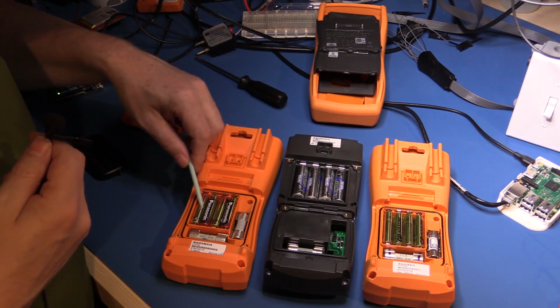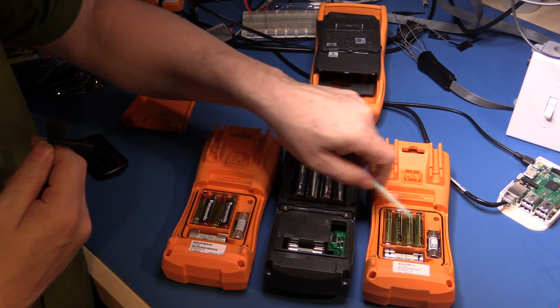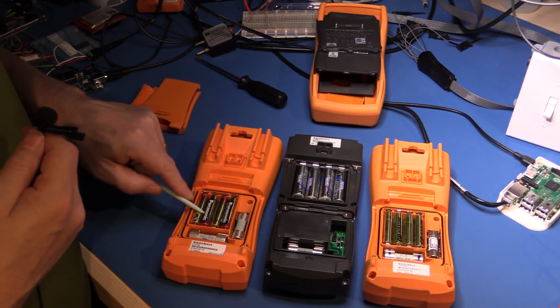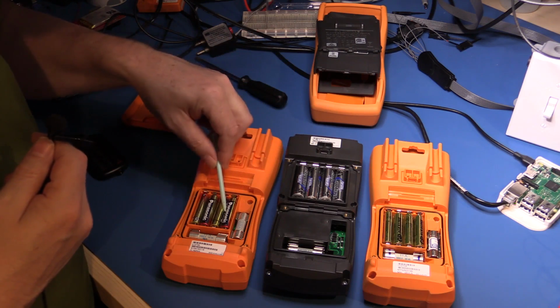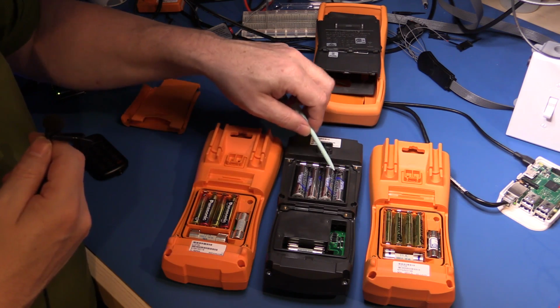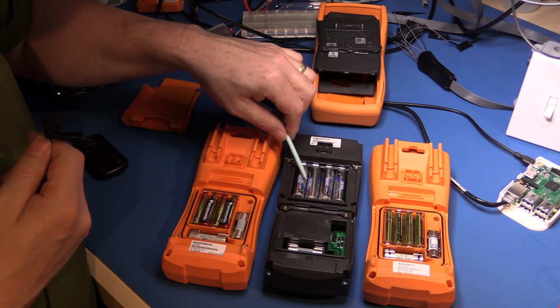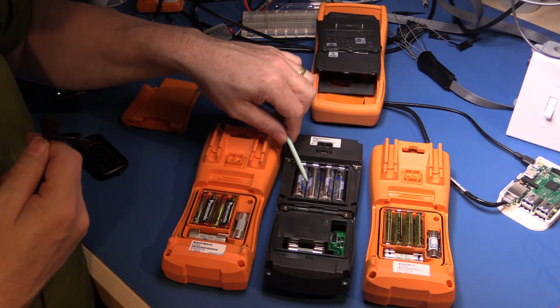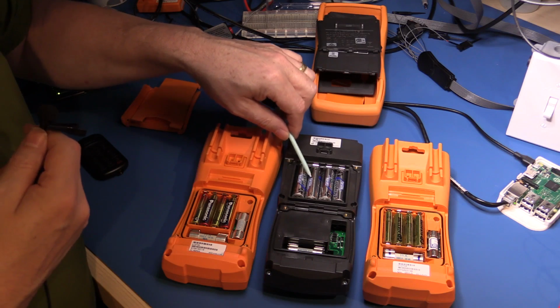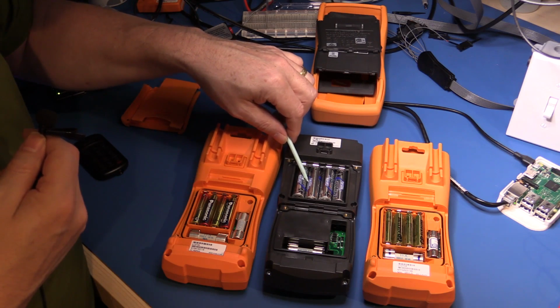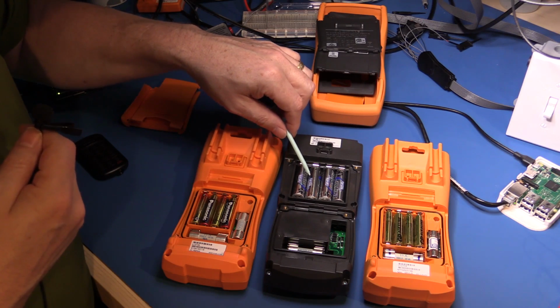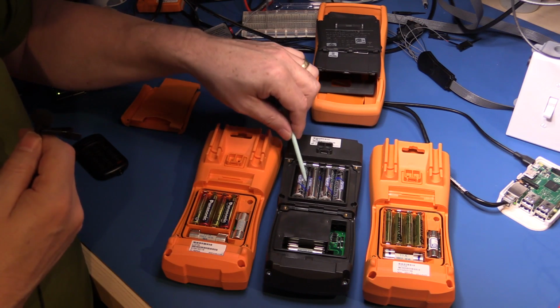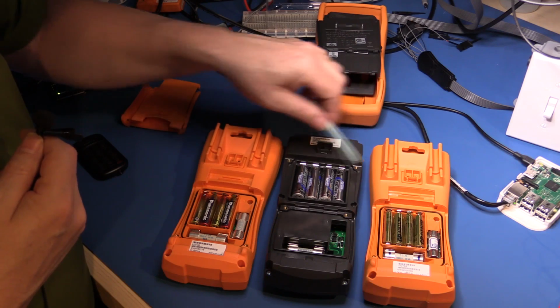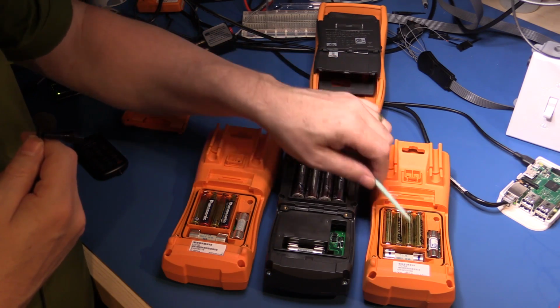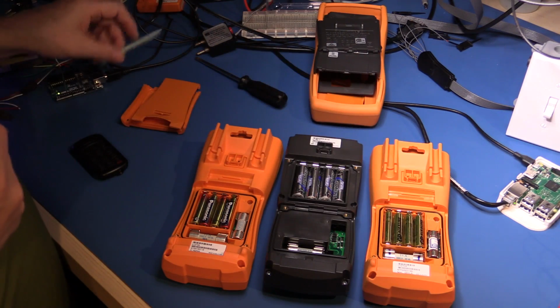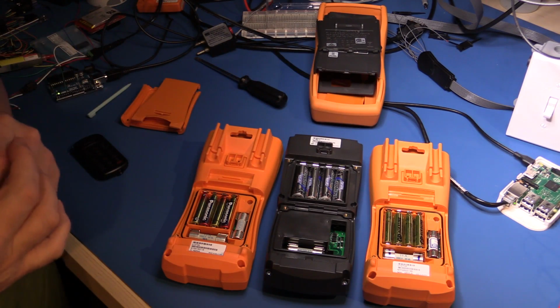And the batteries are in here, and in both of the 1273 and 1272, they're AAA regular alkaline batteries, whereas in the 1461, the batteries are lithium to give us the longer life and also a lower temperature operation range, because this meter is IP67 rated, and it can go down to about minus 40 degrees centigrade for operating. Now, obviously, if you took one of these into that kind of temperature with regular alkalines, the batteries would just cease functioning. So anyway, let's continue.